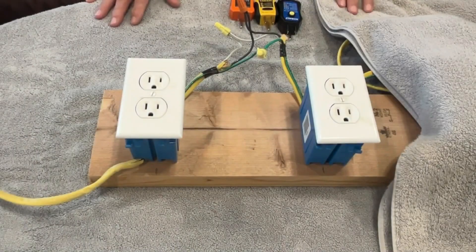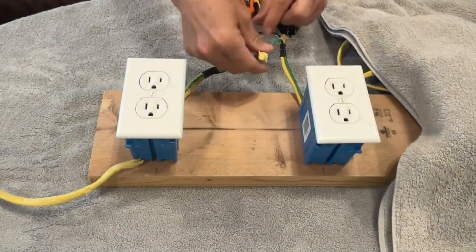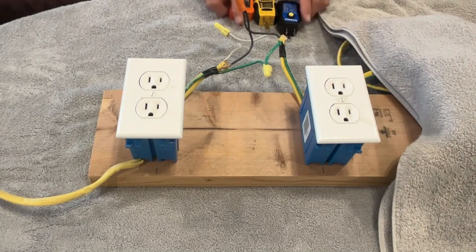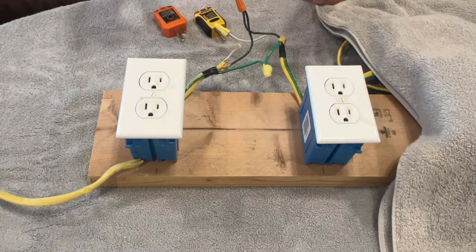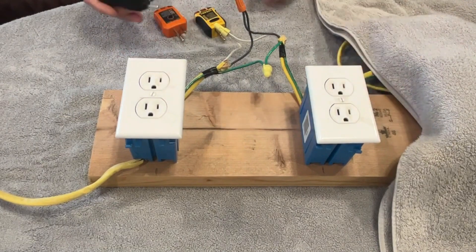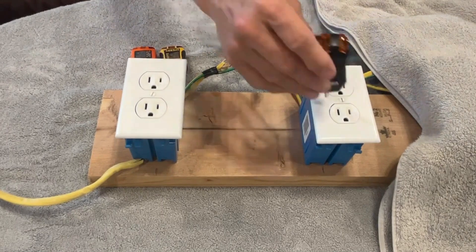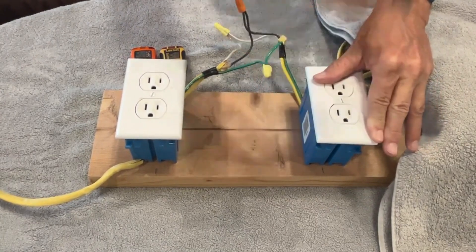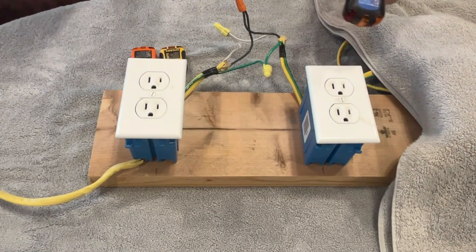Here's part of my test board. You can see green to green, black to black, white to white — so this is currently wired properly. I've got three different testers: a Kobalt, a Sperry, and a Klein, and they all work identically to each other. Both lights light up, and according to the legend, these two lights indicate that it's wired correctly.